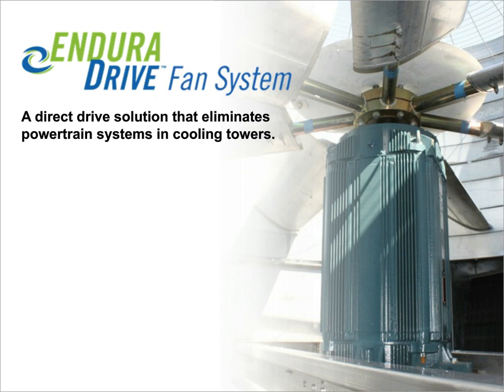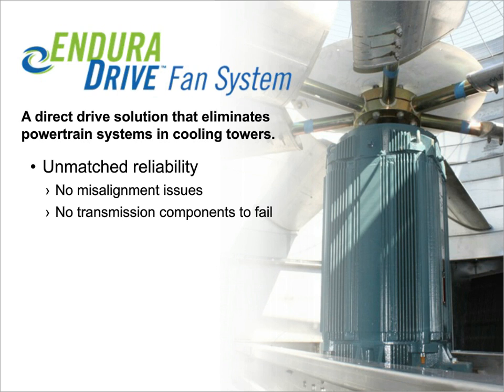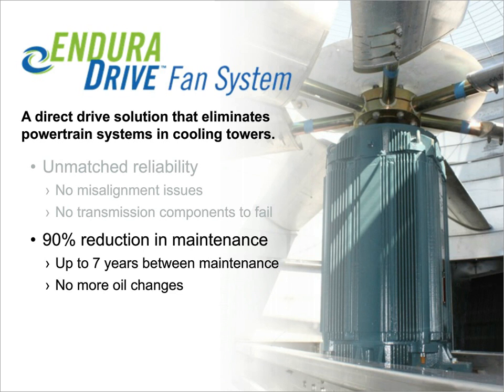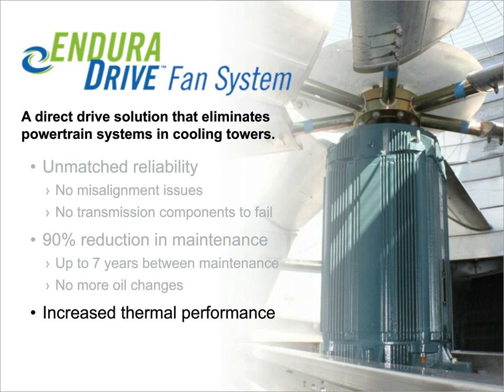The direct drive system, in general, requires maintenance once every 17,000 operating hours, and based on typical building operations, that's a 5 to 7 year maintenance interval. Maintenance is very easy also compared to both belt and gear. All you have to do is grease the motor bearings instead of performing messy oil changes, alignments, or even replacing belts. This is all expensive and time-consuming, and can really reduce your planned downtime. Since there aren't any mechanical losses, direct drive also allows for increased thermal performance, which is great because it can either lower your fan horsepower or reduce the size of the tower that's even required on site.